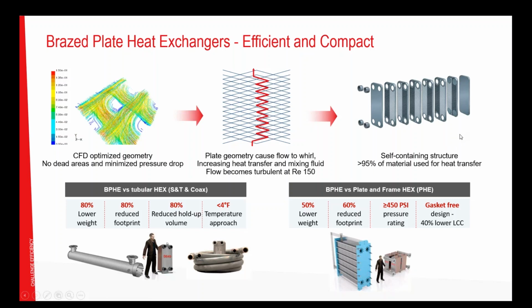And the third advantage that we'll look into now is the self-containing structure of a brazed plate. Between two plates, stainless steel and stainless steel, we have the filler material, which is typically copper, even though it can also be all stainless, as I said before. During the production process, there is stainless steel and a very thin layer of the bonding material, in this case copper. When we put this in the furnace, the copper becomes liquid and connects to the contact points via the capillary forces. When the temperature goes down, the copper becomes a metallic glue that makes all these plates stick together. That means that there is no need for any type of bulky frames or anything else that just takes up space and weight.